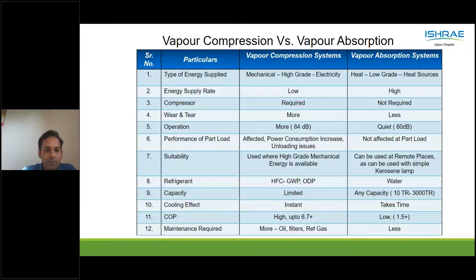Somebody has also asked me many times about the difference in COP or efficiency. Our vapor compression cycles, like centrifugal chillers, have a COP of 6.7 plus. The COP of vapor absorption machines is quite less, because it requires low grade heat in large quantities, restricted to around 1.5 plus. Since there are no moving parts, no oil, no filters, and no refrigerant gas leakages, vapor absorption machines require very little maintenance.